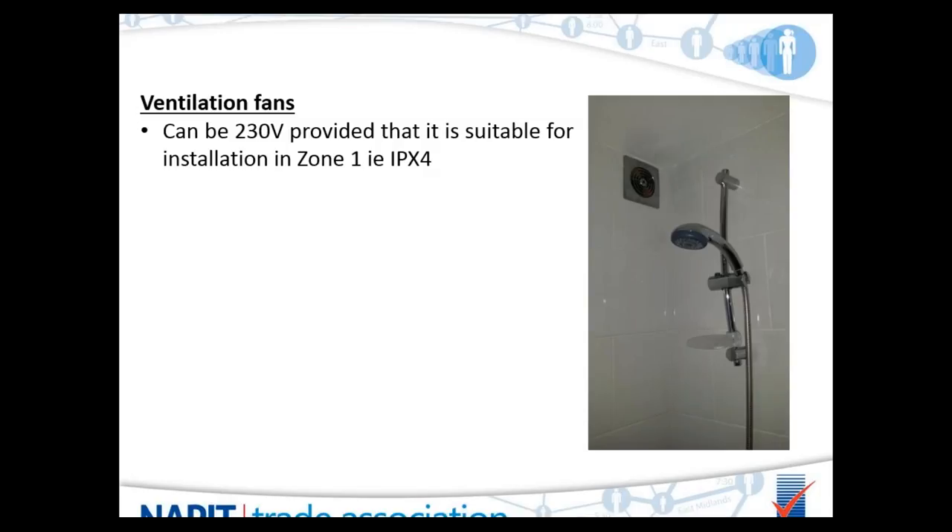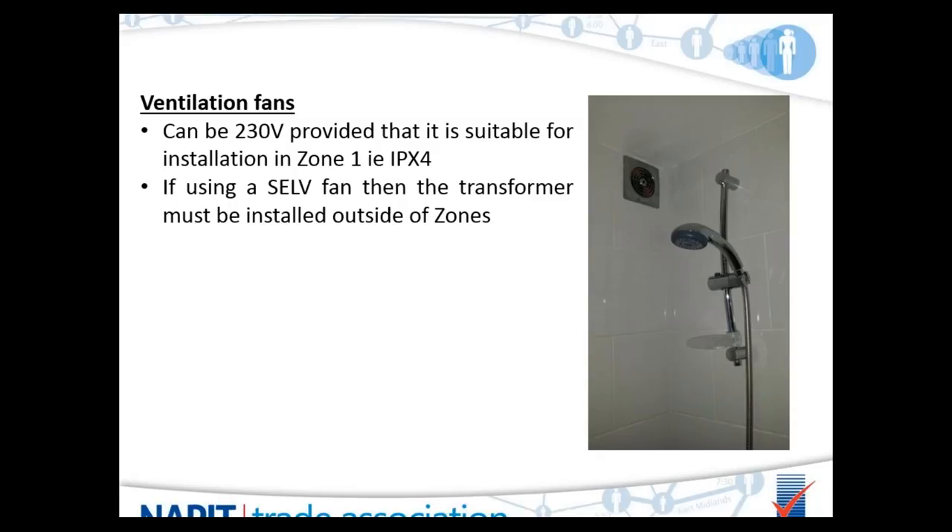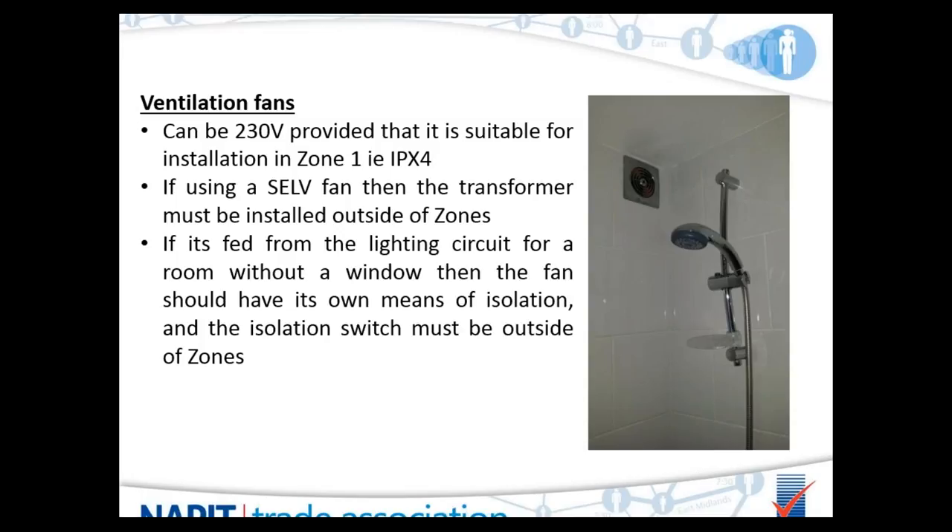Regarding ventilation fans — can a 230 volt fan be put in zone 1? The answer is yes it can. Again, it has to be IPX4 as per the manufacturer's instructions. If you're going to use a SELV fan, the transformer must be installed outside the zones or in roof voids. There's also a building regulation — not an electrical regulation — stating that in a room containing a bath or shower without natural light from a window, there should be an isolator for the fan to enable it to be worked on while the room remains in full artificial light.